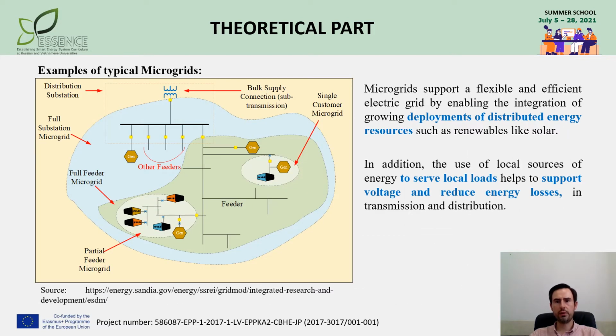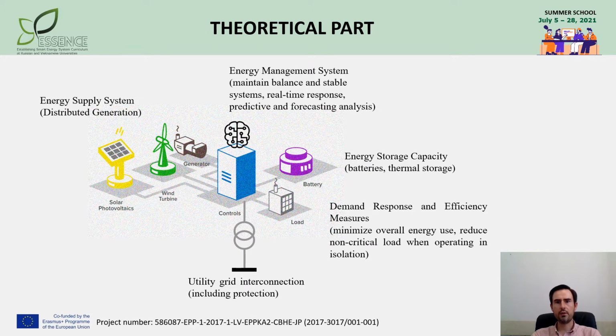The microgrid boundaries shall be defined with respect to how many loads can be supplied by local energy resources, and the goals solved within these boundaries, like integration of distributed resources, support of critical loads, reduction of losses, improved voltage profile, etc. As you may see from the slide, a source connected to the bus of a distribution substation and serving all of the feeders can form a full substation microgrid. While if connected close to the exact consumer and covering their own needs, it may form a single customer, partial, or full feeder microgrid.